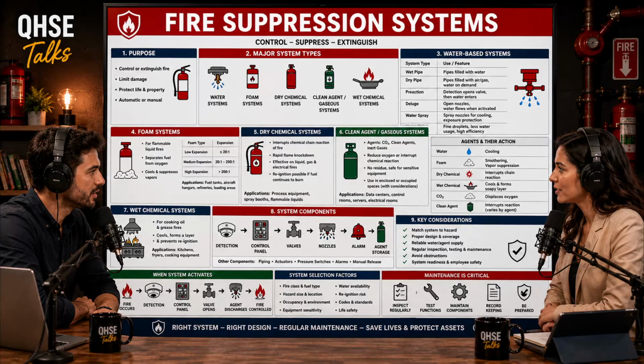So how do we solve thermal lag? That's where the rate of rise detector comes in. It doesn't look at the absolute temperature, it looks at the speed of the temperature change. So it's looking for a sudden spike. Right. It usually contains a small air chamber with a flexible metal diaphragm. Normally, as the room slowly warms up and cools down, a tiny bleed hole lets the pressure equalize. But if a fire flashes, the temperature spikes rapidly. And the air expands too fast for the bleed hole. Exactly. The pressure builds up instantly, pushes the diaphragm up, completes the circuit, and sounds the alarm.